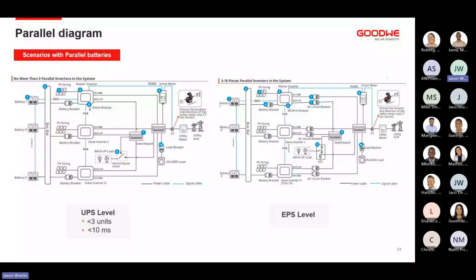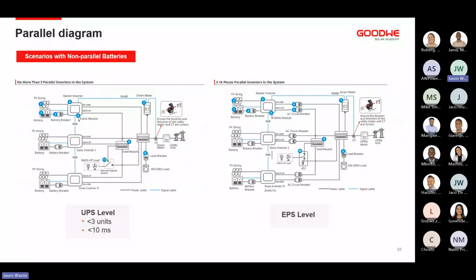And then you can parallel the inverters with non-parallel batteries. So if you have batteries that are different sizes per inverter, you can still parallel the system with each set of batteries connected separately. There are two levels of how the changeover process will then work. You have UPS level switching and then obviously EPS level switching. So if you have 3 inverters or less, you will get your UPS level changeover, so less than 10 milliseconds, you essentially won't notice the power dip at all. Whereas if you have any more than 3, up to 16 units with the ES Unique that you can parallel, the changeover will be a little bit longer.